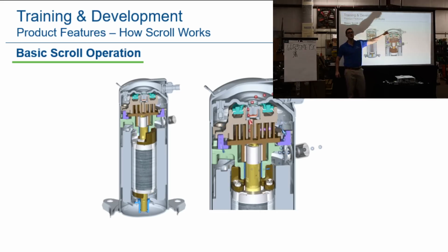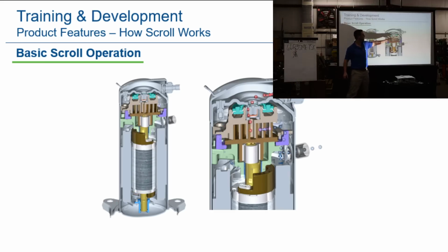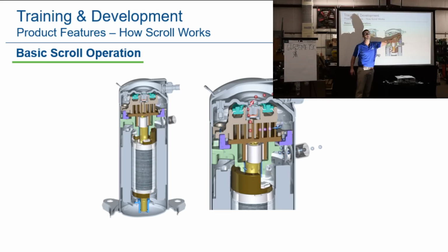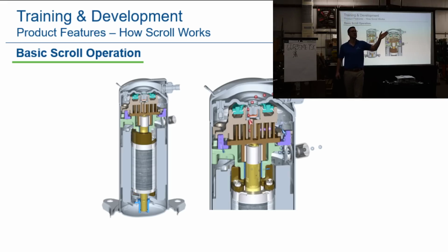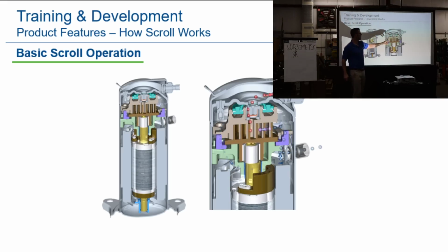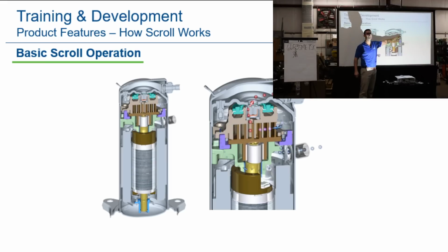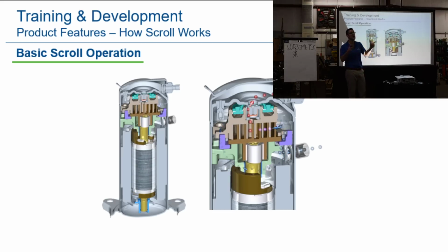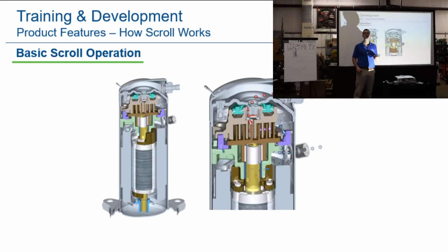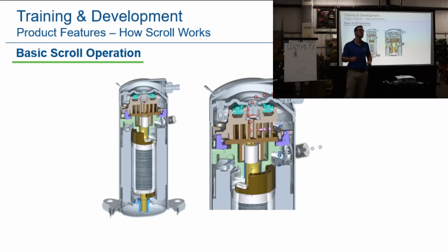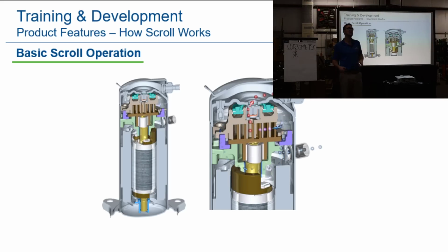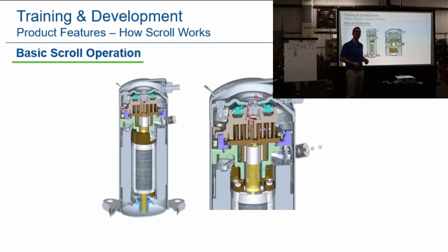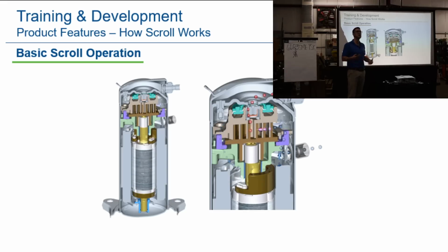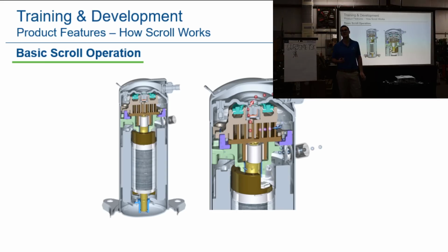But one thing I've seen: if you look in the AE bulletin on this application, we have spring type, and then we have just floating disc type. Depending on our refrigeration compressors, they'll all have the spring type. Some of our AC will have a floating one. So depending on the application, you might have to add a discharge check valve. You'll only find that in the application engineering bulletin. Somebody could install the compressor, cut out the discharge check valve when they do, and then all of a sudden you're running, and you lead to another failure potentially.